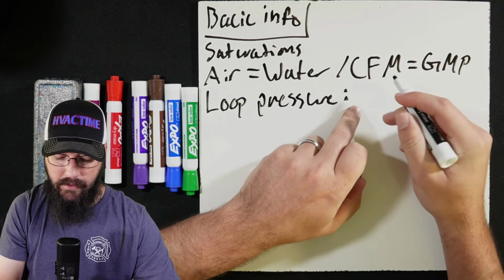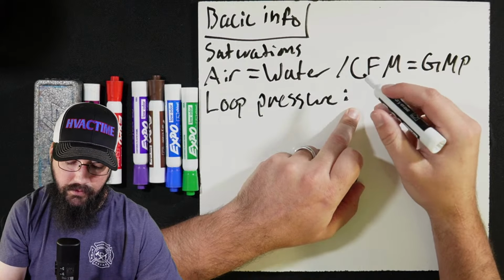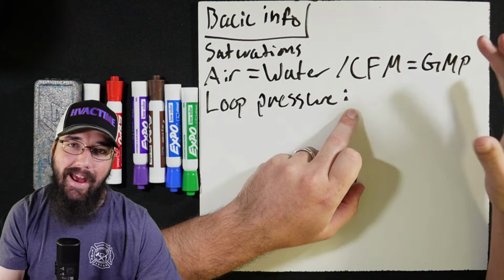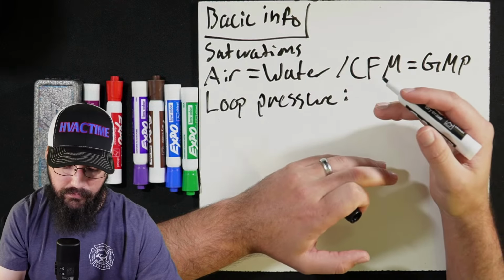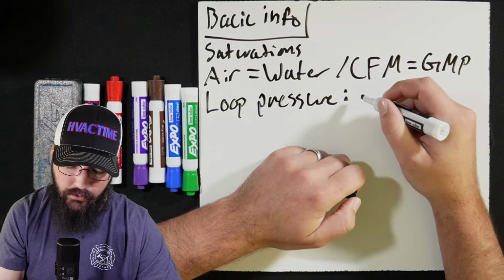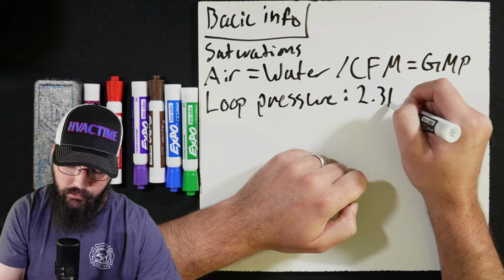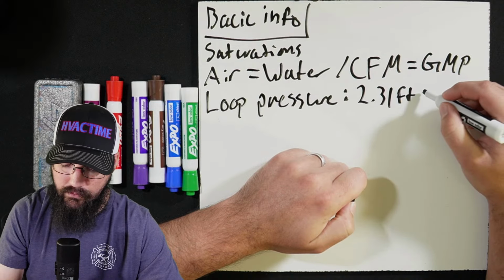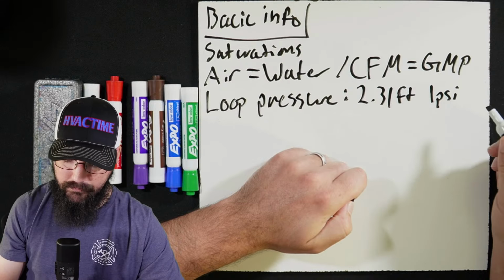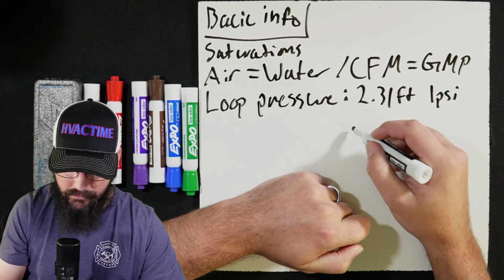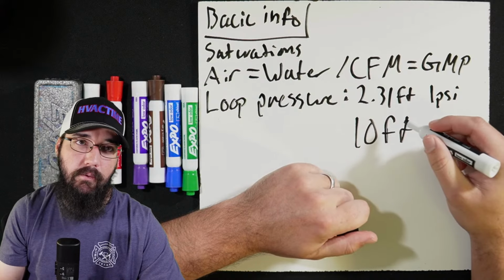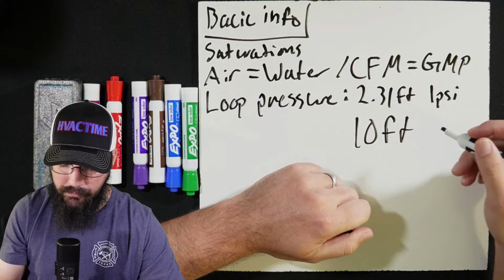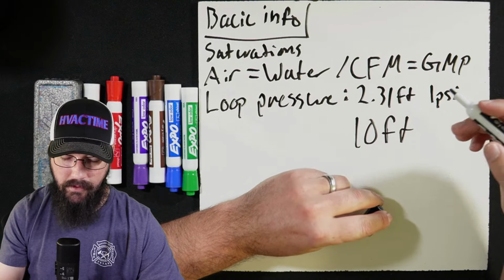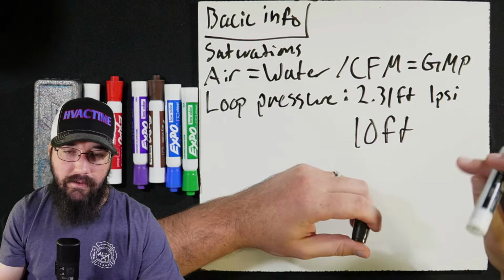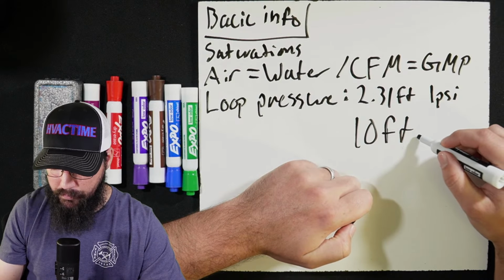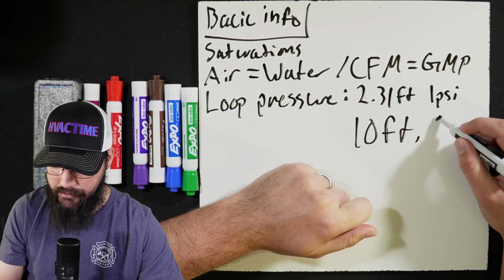The way that I do this from a baseline perspective is we want to know what our loop height is, and then I like to add 8 to 10 psi to that to get us above our head weight pressure. So for every 2.31 feet of height, we have 1 psi. Okay, so if we had a 10-foot building and the equipment was, say, on the ground, say the chiller and the pumps were on the ground, there was equipment in the ceiling of the building, and so there's a 10-foot separation where we've got a total of 10 feet of vertical height, then that would make a loop pressure that I would expect at minimum pressure, okay, a minimum pressure of 23.